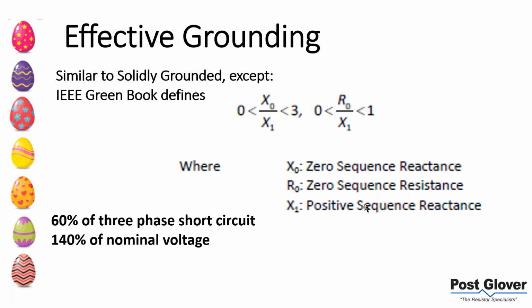When you achieve this, in terms of voltages and currents, you're going to get about 60% of your three-phase short circuit current and about 140% potential overvoltage of your nominal voltage. So it's better for sure than solidly grounded. There are some limitations. Obviously, these are still high numbers, so there are still issues that can happen. But they are limited, relatively speaking.